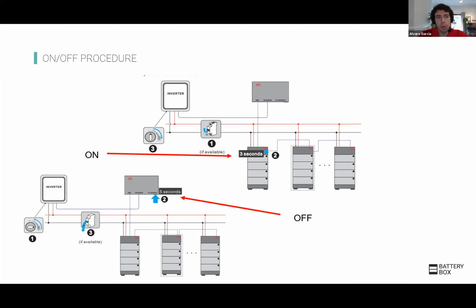The switch on and off procedure is slightly different. The BMU doesn't have its own power; it's powered by the batteries. So to switch on the system, you just need to press on one of the batteries. That battery will power the BMU, and it will power all the rest of the batteries communicating with that first battery. Once you've done the commissioning, you can switch on the inverter. For switch off, it's similar, but you can use the BMU to switch off all the batteries, just by pressing 5 seconds on the BMU, it will switch off all the batteries connected to it.